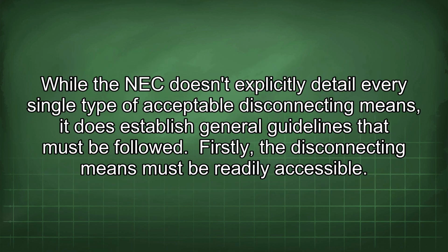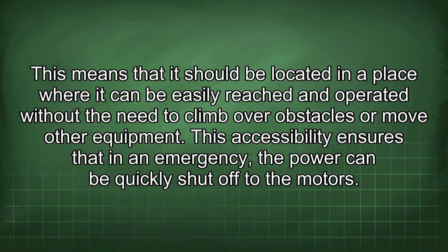While the NEC doesn't explicitly detail every single type of acceptable disconnecting means, it does establish general guidelines that must be followed. Firstly, the disconnecting means must be readily accessible. This means that it should be located in a place where it can be easily reached and operated without the need to climb over obstacles or move other equipment. This accessibility ensures that in an emergency, the power can be quickly shut off to the motors.